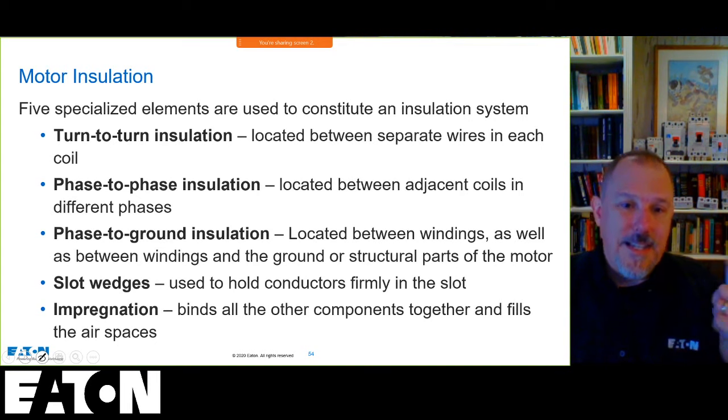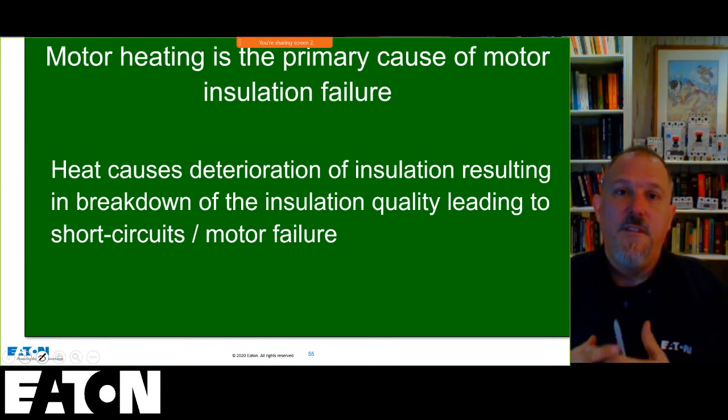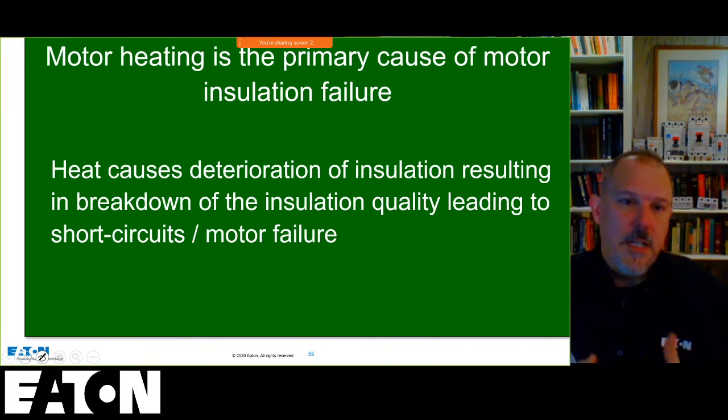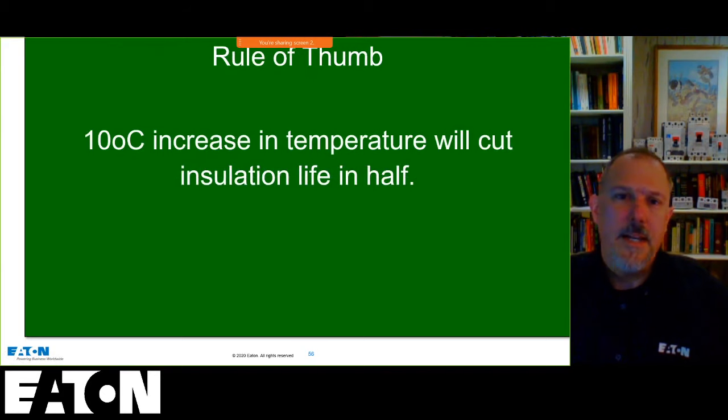So motor heat is the primary cause of failure of insulation. It deteriorates the insulation. It could break down your bearings, the lubrication inside of the motor, etc. A rule of thumb: a 10 degree C rise in temperature will cut the insulation life in half.